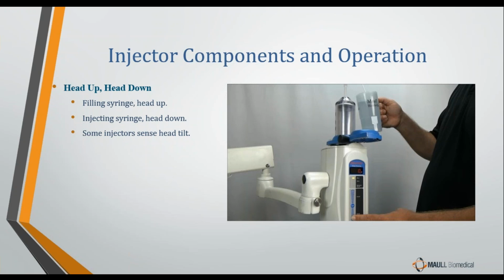Well, if I understand the question, the PM for contrast injectors is annual. If you're asking how long a PM takes, it takes roughly 1 hour. Sometimes it can take 2 hours. I'll talk a little bit more about that later on. It really depends on how much cleaning is needed. The operators are supposed to clean the injector on a daily basis. Yeah, I'm not thinking that happens every time. So basically, you're looking at 1 or 2 hours for a PM. Typically 1 hour. 2 hours is kind of long, but it could stretch that far. And then the manufacturers do recommend it be an annual event. There's really no need to do it more than once a year unless excessive cleaning is needed. And what was the last part of the question?